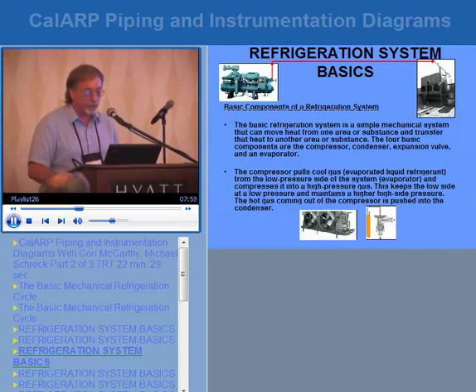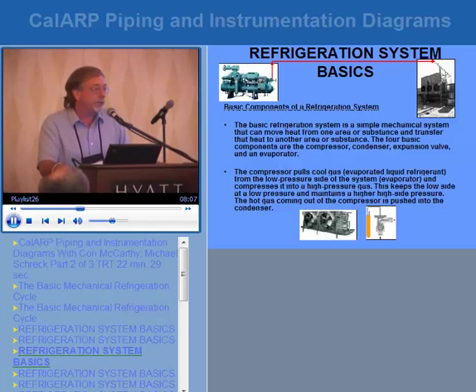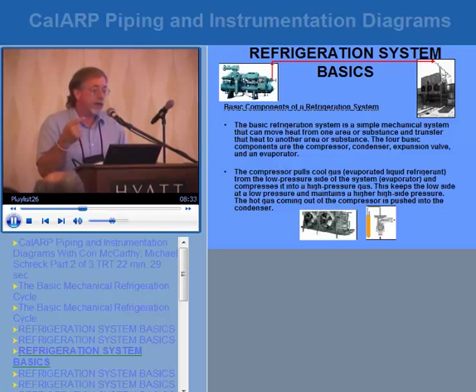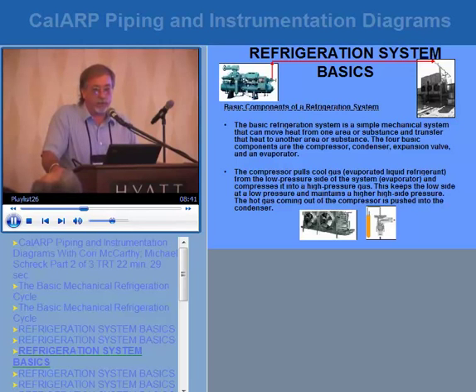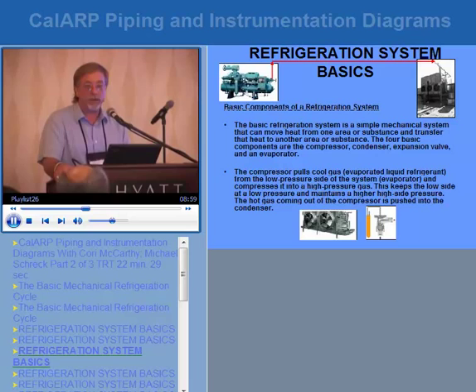From the condenser, the refrigerant drains into the high-pressure receiver — your main liquid supply or storage tank. One thing you'd like to see on P&IDs is that major valves are not only labeled but identified effectively, such as with what we call the king valve. Sometimes fire departments think that once they close the king valve everything is safe, but there are other valves that send ammonia to the process. The king valve controls the liquid side, but we also need to remember the main hot gas valve. We've had incidents where people isolated a system using the king valve and the system then went into defrost — sending hot gas at high pressure to that same location — resulting in direct ammonia exposure.